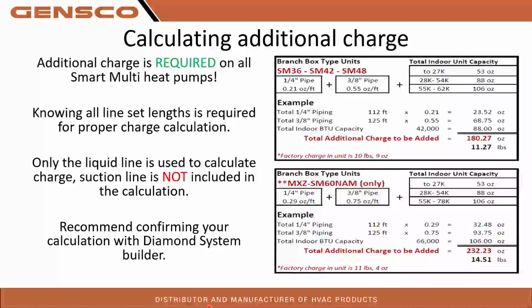So remember that. Knowing the line set lengths on your system is going to be required. It's crucial. You have to know those line set lengths in order to properly charge this thing. When you're charging it, you're only charging based off of the liquid line. You're not taking the suction line into account when you're calculating charge. It is all based on liquid. So what you would do is, we'll use this SM60 here as an example.